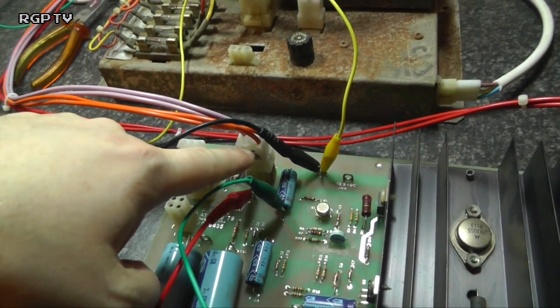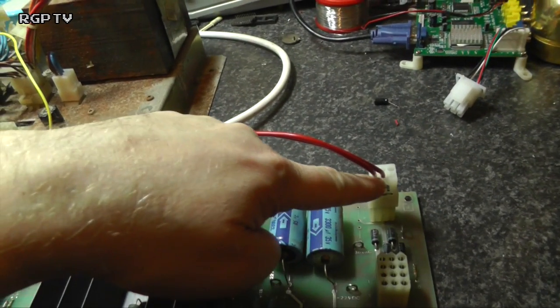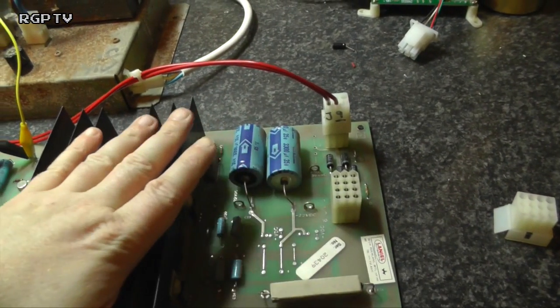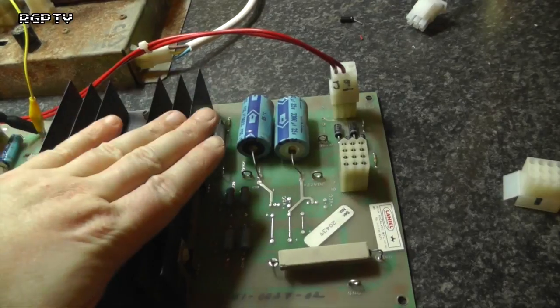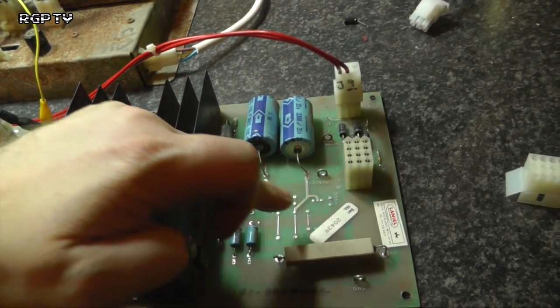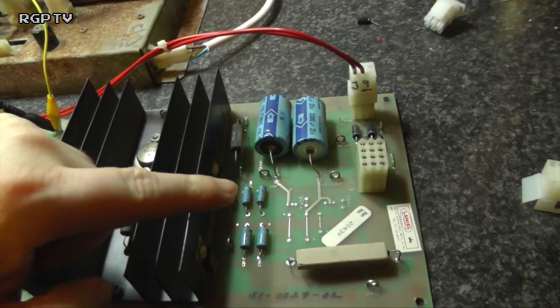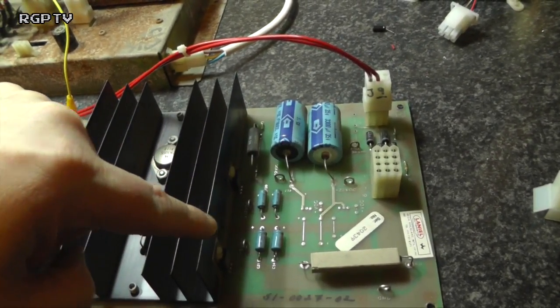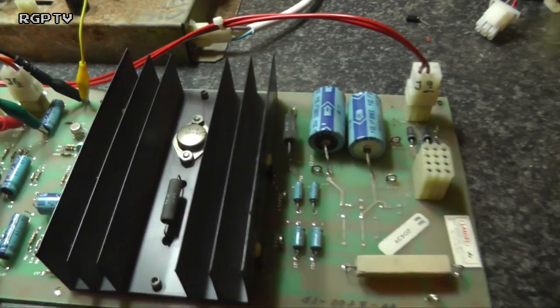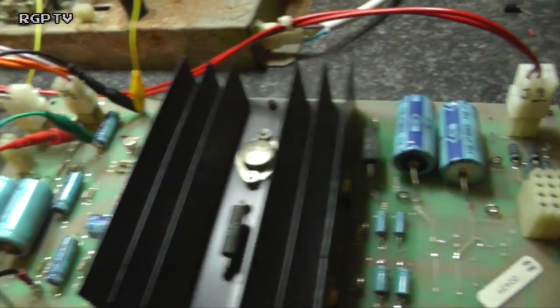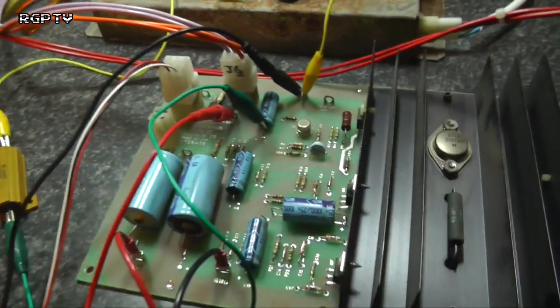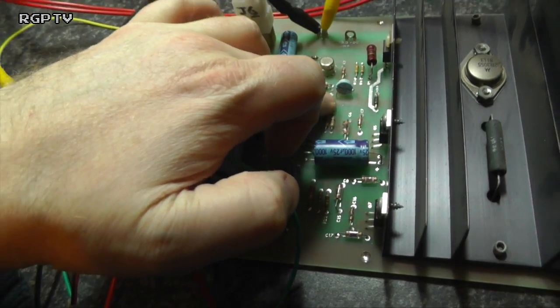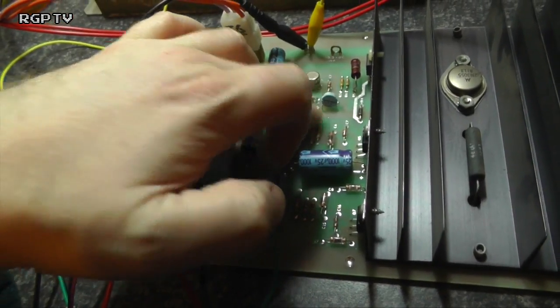Your 36 volts stays on this side and is mostly responsible for generating 22 volts, and if modules were plugged in there'd be plus and minus 15 volts. There's also 12 volts and minus 5 test points. I've been around the board and checked those, and I'm happy with what that's outputting.